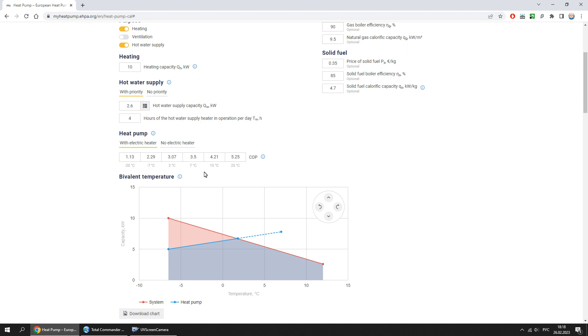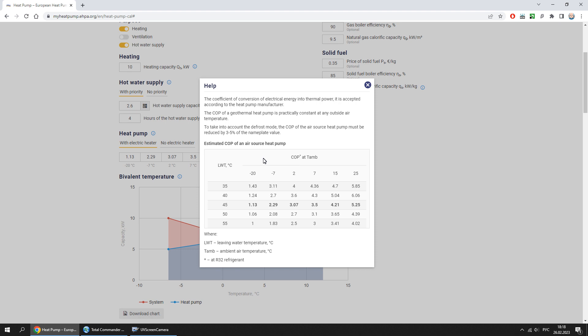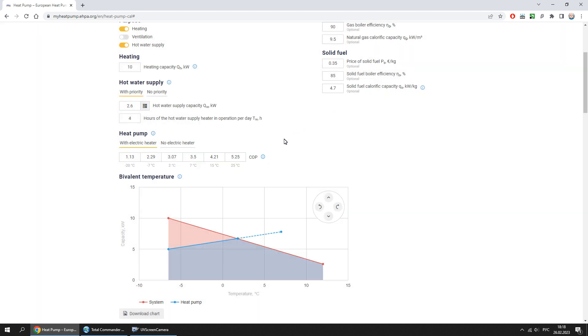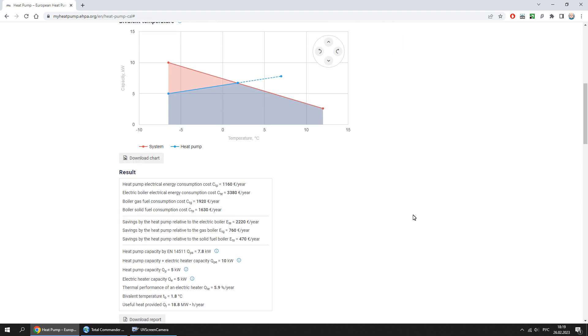Here it is necessary to enter the COP of the heat pump at the appropriate outside temperature. The COP value can be taken from the technical guidelines of the heat pump or from the help section. The bivalent temperature is the switch-on temperature of the electric heater. It is recommended to adjust the bivalent temperature until the thermal performance of the electric heater during the bivalent period is about five percent. Let's adjust the bivalent temperature.